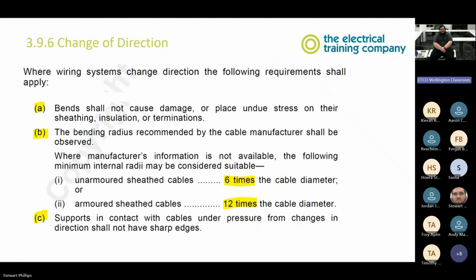Cool. And supports in contact with cables under pressure from changes in direction shall not have sharp edges. So if we're pulling something tight along the cable tray, making a tight bend along the hard wall, we need to make sure there are no sharp edges, or we put extra mechanical protection in place.